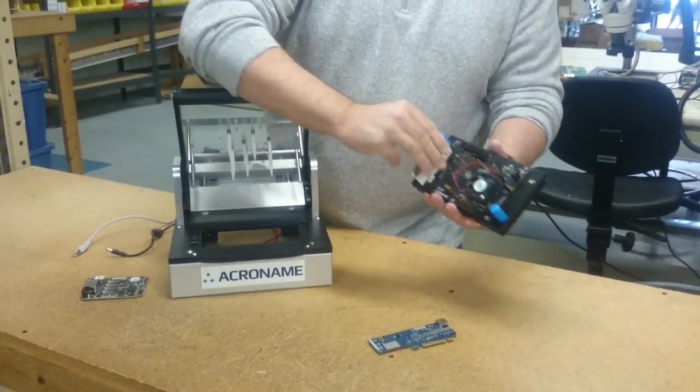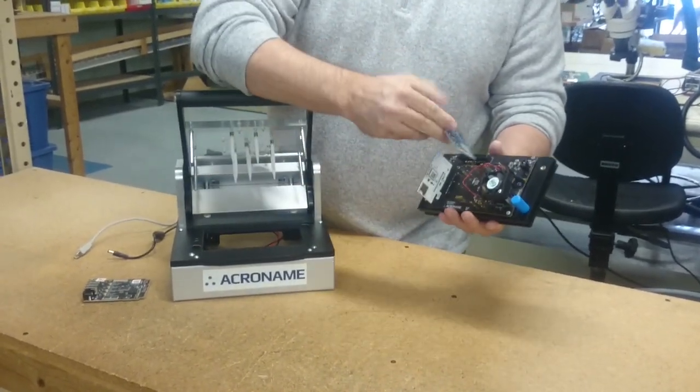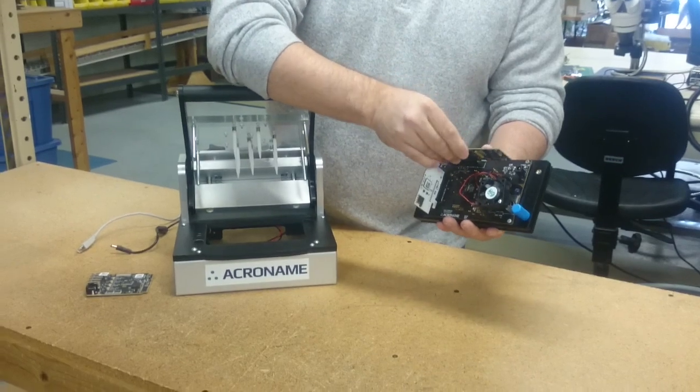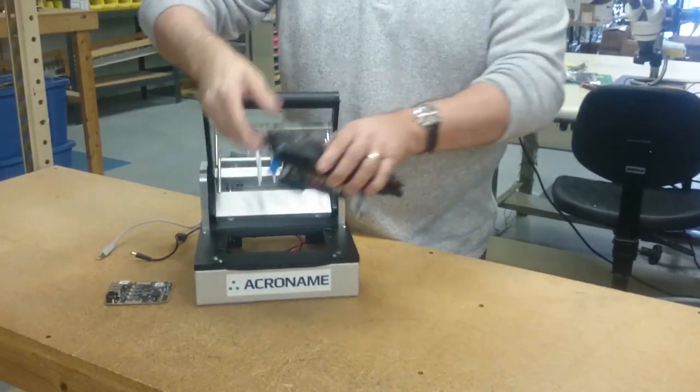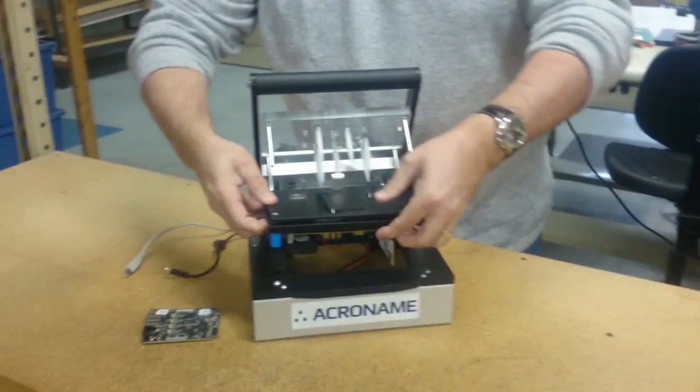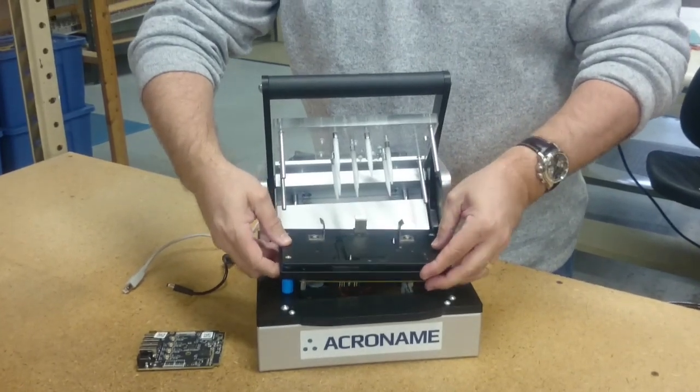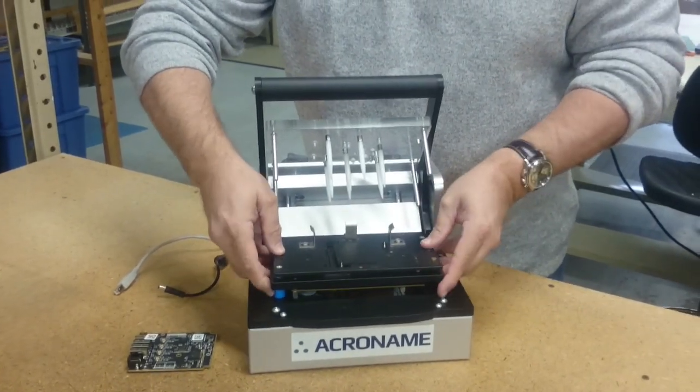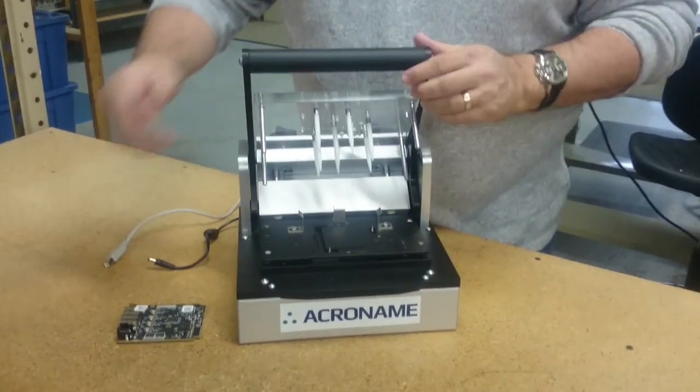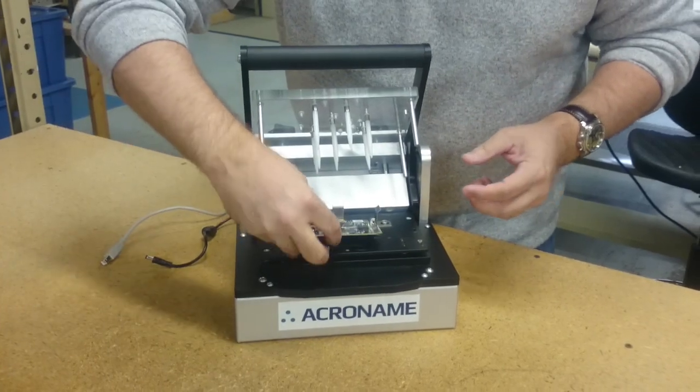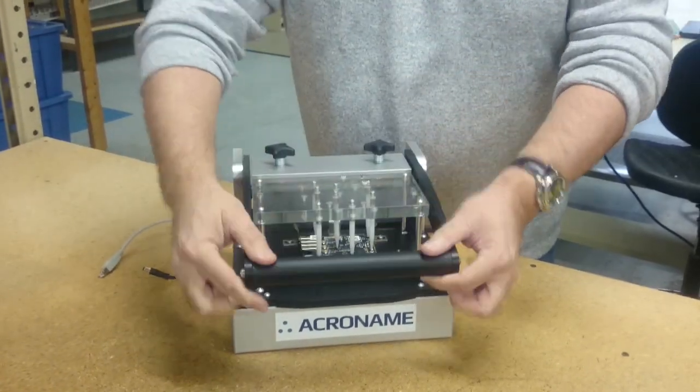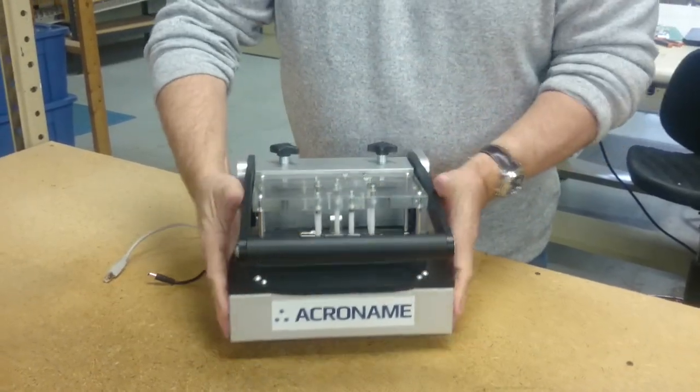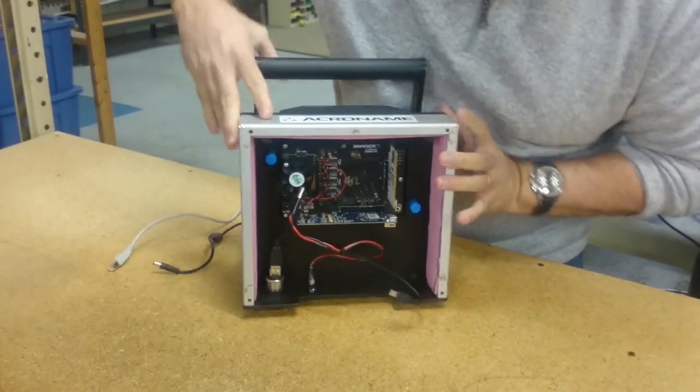Now we're ready for another DUT. So we grab a new ATS module, insert the off-the-shelf MTM modules for use in that tester, and we're all ready for another DUT. Drop in the cartridge. We'll plug in power and USB internally.